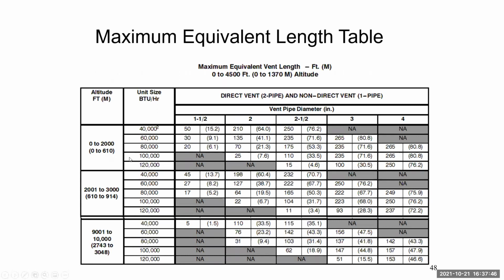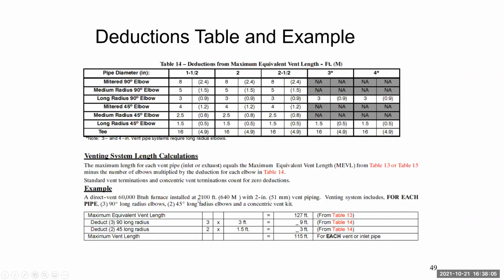With this being said, also pay attention to your altitude where you're at. It doesn't need to be 100% specific to the exact address. Get at least your city and know about what your altitude is, because that's critical, and you'll see the differences as you look through these charts. So pay attention to that. Also know your differences of your 45s and your 90s as far as long radius, medium radius, and standard. Because you'll see the difference here. I mean, just a long radius and medium radius 90 is a 2-foot difference. So pay attention to that, and know what you're working with.